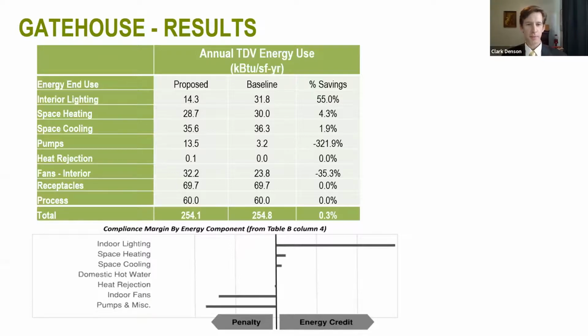In reality, the building is probably operating much more efficiently than the model suggests. The reason for this is that this particular version of CBECC-Com that was used for the project couldn't model variable speed fans in water source heat pumps. And while we could have probably used some workarounds and post-processing to show slightly higher compliance margin, as we had done during earlier iterations of the model, our final model was able to demonstrate compliance without such workarounds.